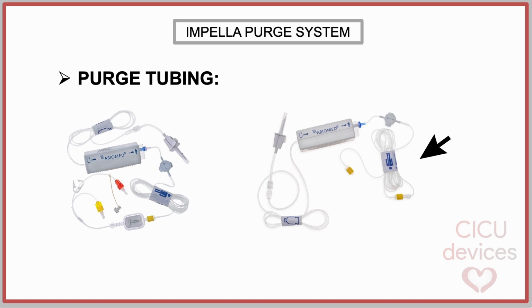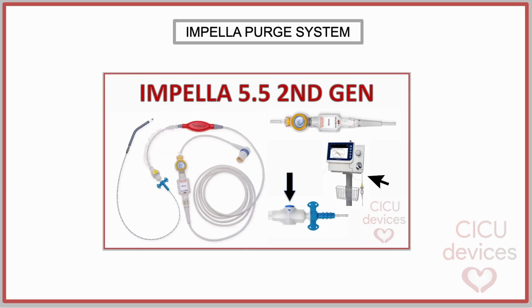In the most recent design, the purge tubing no longer includes the Y extension and instead features a modular configuration. This design allows the use of a 3-meter tubing segment for the Impella CP, or the removal of part of the tubing to achieve a shortened length of approximately 20 centimeters for use with the second-generation Impella 5.5. You can find more information in our previous video on the second-generation Impella 5.5. The link is available in the description.